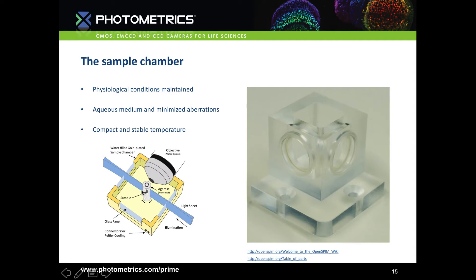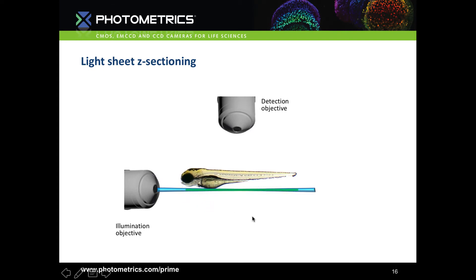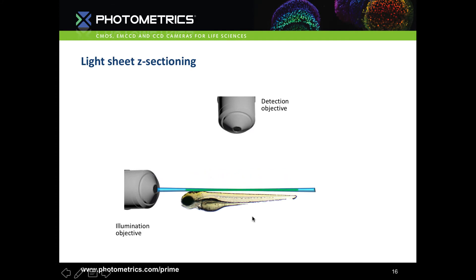The sample can then be moved in XYZ and rotated. To generate Z-stacks, you simply move the sample through the lightsheet beam. You only detect fluorescence from the area illuminated by the lightsheet. By adjusting the width of the beam waist you can get larger or smaller step sizes. Smaller steps give higher resolution but take longer and generate more data; a thicker beam with fewer steps cuts down on time and data when high resolution isn't needed.